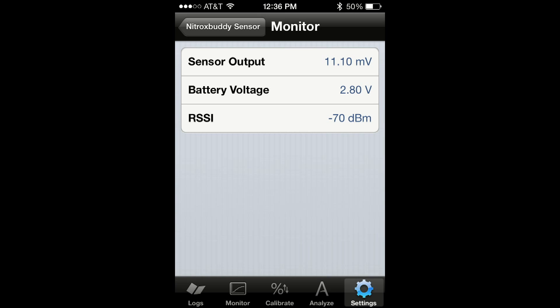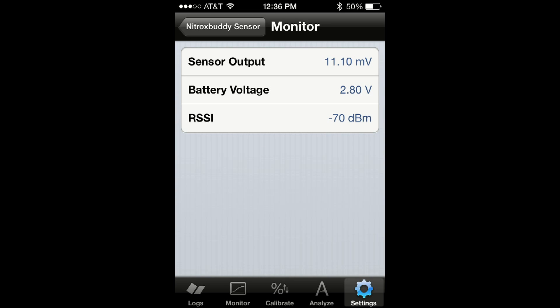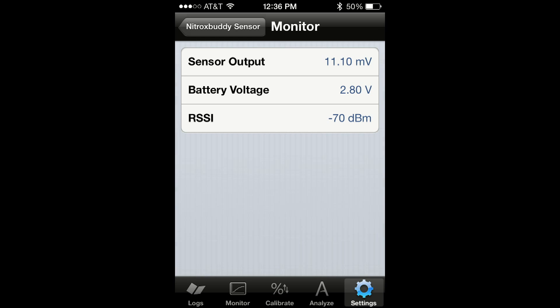While leaving the nitrox buddy standing by itself, watch the sensor output value for several seconds and you will notice that it will tend to stabilize around a specific number. Once the value is stable, tap on calibrate.